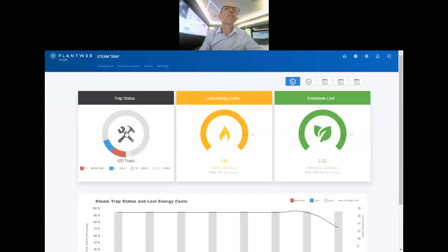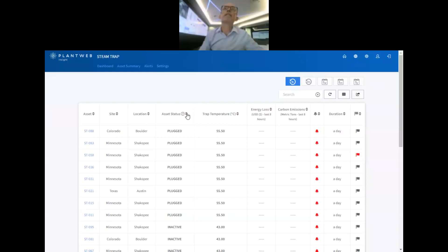In this plant, I'm monitoring 100 steam traps, and I can see 11 of them are blowing steam and 9 are cold, trapping condensate. Both are bad. So I can zoom into greater detail and get a summary - an alarm summary, but not a process alarm summary, an equipment alarm summary. I can see the asset status: these are the ones that are blowing through, and these ones are plugged, trapping condensate. So this is descriptive analytics - it tells me which steam trap has a problem and what's going on, and it also tells me my energy loss and the carbon footprint it's causing.